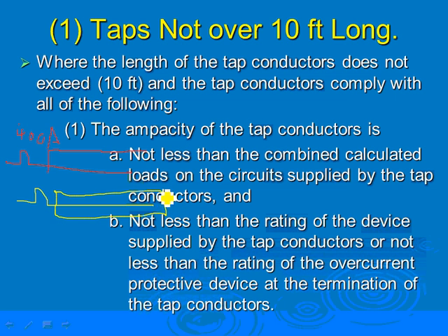Here's my circuit. Here's my gutter. Here's my 400 amp circuit breaker, and I need to tap this 400 amp circuit breaker. So I went here all the way to a fuse disconnect, and here's my fuse disconnect. I put my fuses in it and tapped it with a motor here, and the distance from here to here is 10 feet. That's what the 10-foot tap is, right?